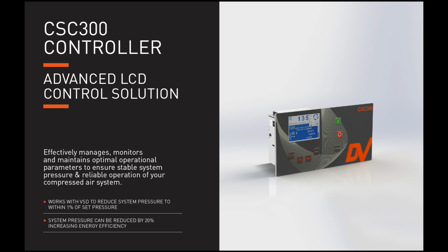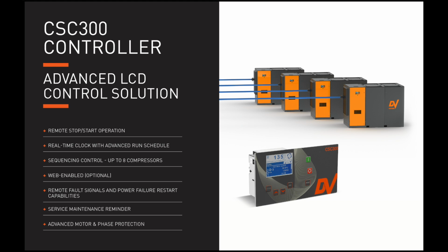It effectively manages, monitors, and maintains optimal operational parameters to ensure stable system pressure and reliable operation. The CSC 300 works with the variable frequency drive to reduce system pressure to within 1% of set pressure. In this way, system pressure can typically be reduced by 20%, increasing energy efficiency. The CSC 300 features remote stop-start operation, a real-time clock with an advanced run schedule, sequencing control of up to 8 air compressors. It's optionally web-enabled and features remote fault signals and power failure restart capabilities and a service maintenance reminder.